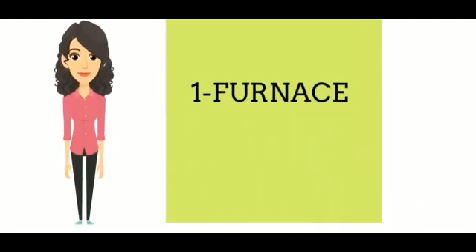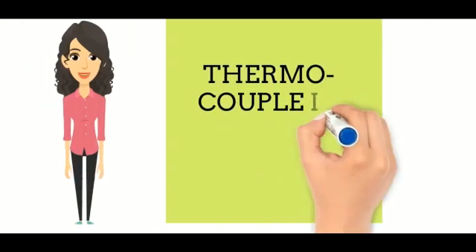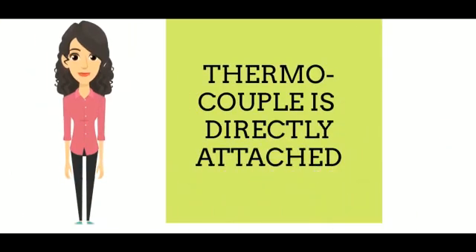The furnace or heating block is the heart of analysis, in which an identical pair of cavities are placed for reference and sample material. Thermocouples are directly attached to the sample and reference to note the temperature difference.